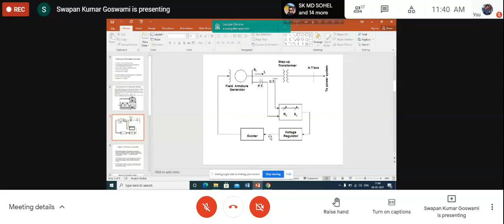Obviously the purpose of this transformer is so that the generated voltage is not very high. Why? Because inside the generator you cannot generate a very high voltage because of the limitation of the size of the generator, how much insulation you can provide inside. So the generated voltage is less. It has to be stepped up, and then it is the transmission voltage of the HT bus. From the high tension bus, that means high voltage bus, the transmission line will go outside the power station.